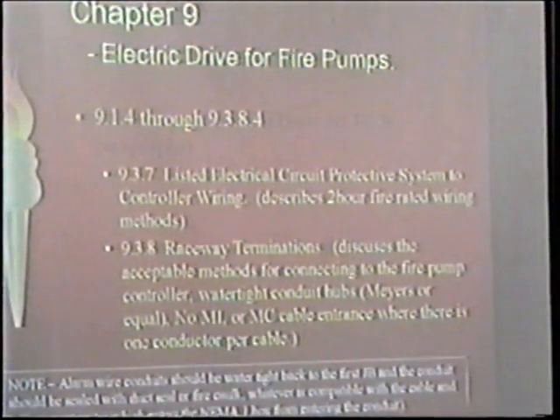To the next slide. Yeah, and you'll probably hear that term, CI cable. It stands for circuit integrity cable, on fire alarms. If you've ever heard of plenum cable, it is designed so that in a fire, the insulation drips off of it in less than 30 seconds. It's Teflon, it just melts away, and the circuit's free to short out. They just don't want the smoke. Well, a circuit integrity cable is the opposite. It's a cable with a ceramifiable silicone compound that, when it gets to 900 degrees, starts a conversion process to ceramic. And it will withstand 1500 degrees for more than 2 hours. So it's designed not to let that circuit fail.